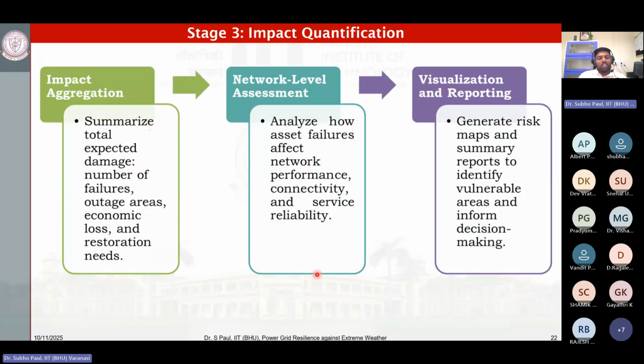Then we'll do the network level analysis. That means some portion of the network is already de-energized. Can we run the rest of the network properly? If we want to run, then what extra effort do we have to take? That means if it is an over voltage condition, then which reactive power absorbers or inductors we have to turn on, and at which locations, or which generators need to be slowed down, or the generation from which generators needs to be cut down. All this analysis we do at the network level. Then we do the visualization of the entire system and we do the report writing.